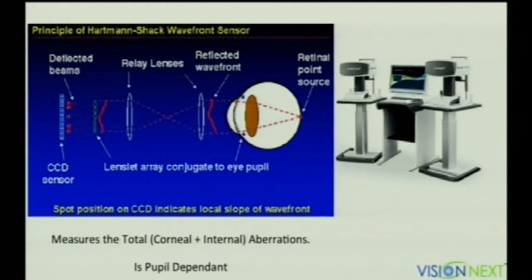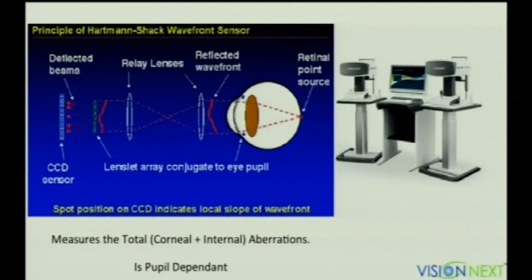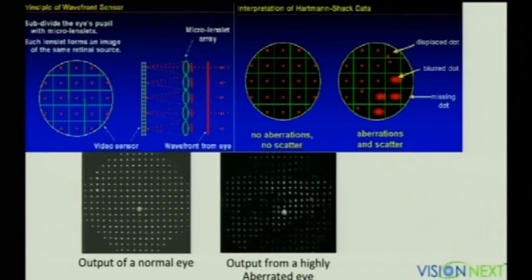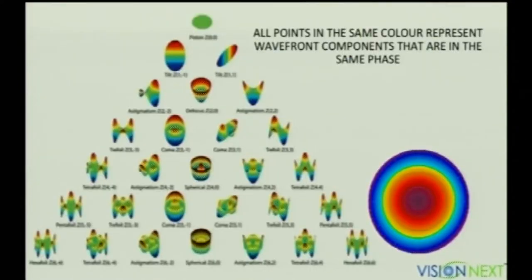The I-Wave is a Hartmann-Shack based aberrometer. A point source of light is focused on the retina; the reflected image passes through the aberrations of the optical system to form a wavefront. This wavefront passes through a series of lenslets, each focused into multiple points. Comparing these with an ideal point of focus shows displacement — an indicator of aberration — or blurring — an indicator of scatter. This is a relatively normal eye's wavefront versus output from a highly aberrated eye.